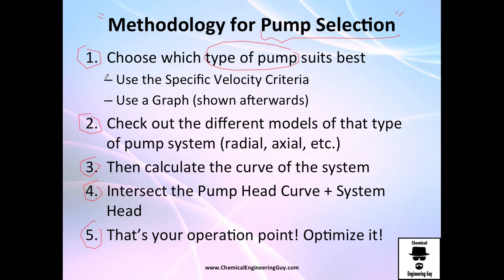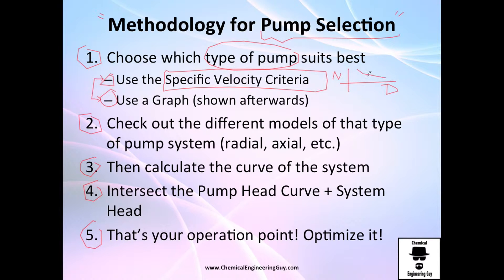There are two common approaches. The first is the specific velocity criteria, which involves analyzing the velocity and diameter of the pump and relating those to choose the best pump from a graph. The second approach is simpler: a graph based on volumetric flow rate and head, where different areas tell you what type of pump to choose.